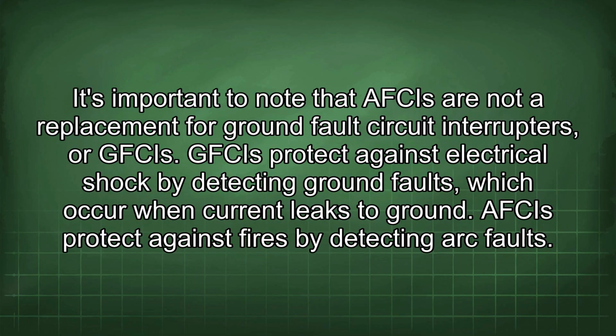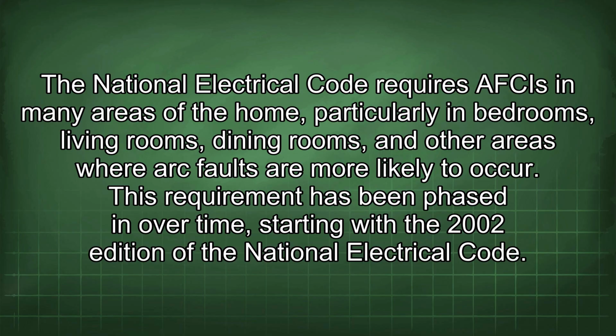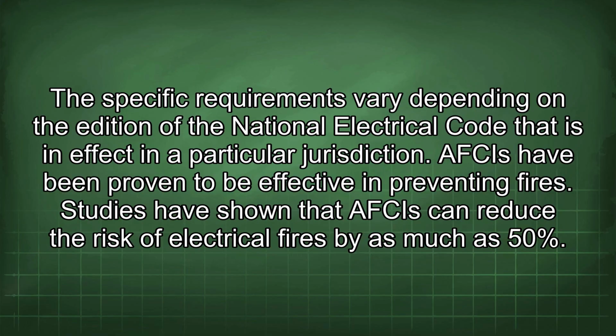It's important to note that AFCIs are not a replacement for ground fault circuit interrupters, or GFCIs. GFCIs protect against electrical shock by detecting ground faults, which occur when current leaks to ground. AFCIs protect against fires by detecting arc faults. The National Electrical Code requires AFCIs in many areas of the home, particularly in bedrooms, living rooms, dining rooms, and other areas where arc faults are more likely to occur. This requirement has been phased in over time, starting with the 2002 edition of the National Electrical Code. The specific requirements vary depending on the edition of the National Electrical Code that is in effect in a particular jurisdiction.